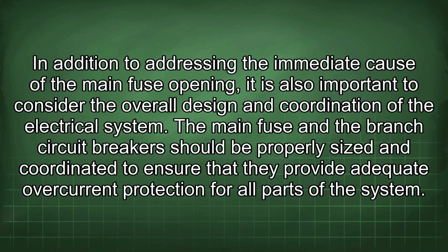In addition to addressing the immediate cause of the main fuse opening, it is also important to consider the overall design and coordination of the electrical system. The main fuse and the branch circuit breaker should be properly sized and coordinated to ensure that they provide adequate overcurrent protection for all parts of the system.